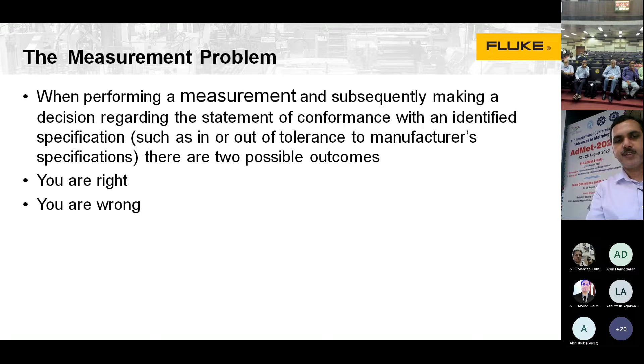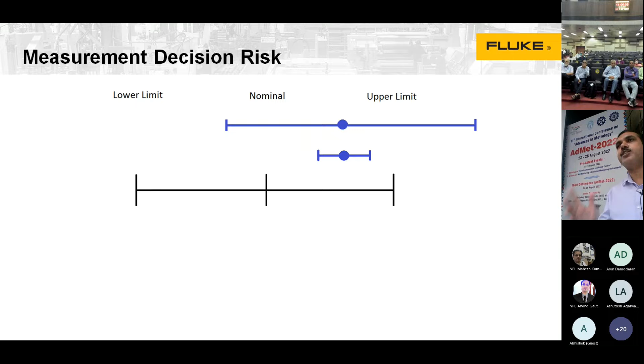So this is the specification limit. At the center, the nominal value, and the lower and upper limit. If the assigned value and the measurement uncertainty are within the lower and upper limit, this is the case of a clear pass. It is within the limits. But if your measurement capability or uncertainty is higher than the tolerance, that is, the lower and upper limit of this manufacturer's specification, and you are giving the decision on this basis, there is a risk that it is a false accept. If you are accepting, it's a false accept.